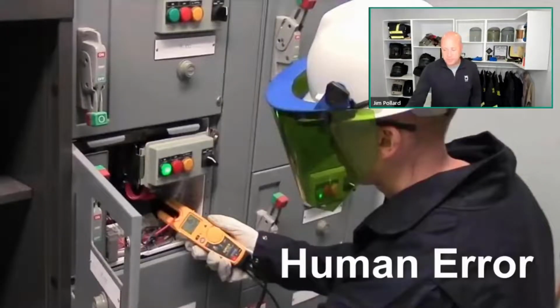Human error. This picture is actually of a video from a manufacturer. I think it's a great manufacturer. However, the worker demonstrating how to use the manufacturer's product is doing so with a hacked PPE system. If you're familiar with the requirements of PPE in NFPA 70E, you can easily see this worker does not have hearing protection. Furthermore, this worker does not have an ARC-rated balaclava.